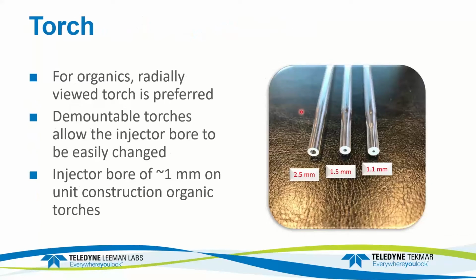Right. And the torch itself, for organics, we said earlier, the radial view is what is preferred. Both the Prodigy Plus and the Prodigy 7 use demountable torches, and that allows you to change the injector bore. For organic solutions and wear metals, typically people will use the 1.1 millimeter, the most narrow, again reducing the amount of material that gets up into the torch. And there are others that are used for coolant. We would probably go to the 2.5 or maybe even the 1.5, depending. There are some different sizes available. People have certain favorites. So for this particular study, we use the 1.1 millimeter injector for all samples.